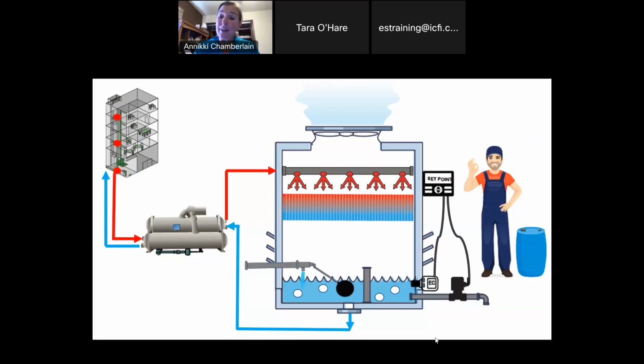Of course, any valve will always, oh yeah, here we got some good ones, faulty valves, always. You can never trust a valve. It may not betray you today, but it will betray you tomorrow. So you just have to know that every valve will eventually fail you. So yes, we could get a couple of valve failures. We have the blowdown valve. That blowdown valve could get stuck open and it's just running water all the way through. So what kind of event would that be? Is that waste or damage?